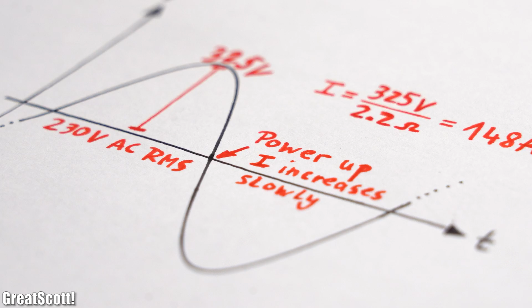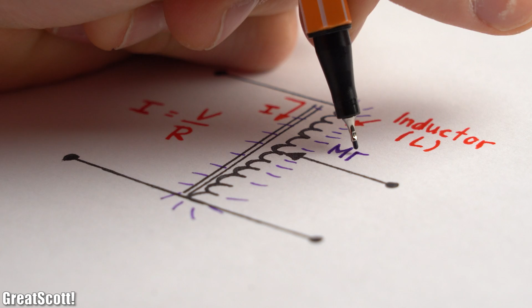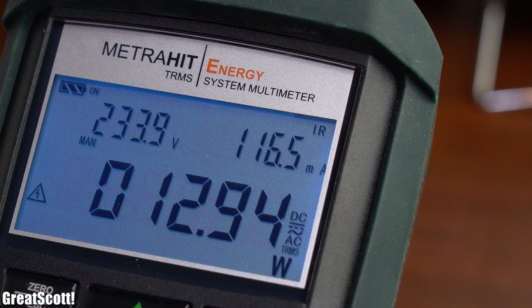That's why the circuit breaker trips. But here's my first solution: if we power the transformer near the zero point, the initial current spike will be much lower and hopefully won't trip the breaker. Due to the now flowing current, the magnetic field also builds up, which opposes the current flow and creates an additional resistance that lowers the current to the previously measured values.